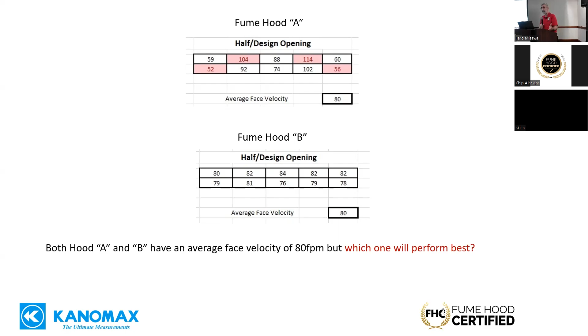Well, if you look at hood A, it's very turbulent because those numbers are all over the map. And so typically, ASHRAE does say the only place there's a fail to it is if there's more than a 10% variation between the high and the low, they tell you the hood's not going to work, so stop testing until it's fixed. So basically what we have is a situation where that first hood is very turbulent. It's not going to contain. So without even getting out FS6 or anything else, I can pretty much tell you that hood will not pass just by looking at the face velocity.